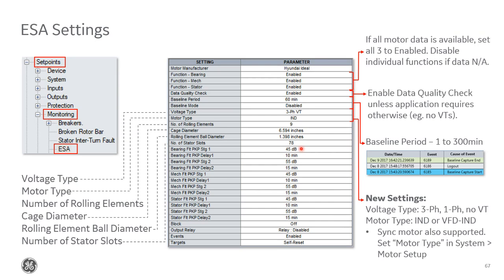Now, the meat of the settings, as I mentioned earlier, are these pickup values and the delays. So you see we have pickups and delays for each of the three categories for bearing, mechanical, and stator. For each of these, we have a stage one, which is an early warning pickup, along with the delay for stage one, and then a stage two pickup, which is more of a serious warning, along with the associated delay for that stage two pickup.